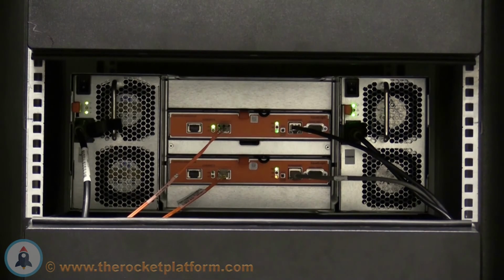In the rear of the machine, you will see the control modules. The faulty control module is in the secondary state now and will have a green light for the PWR and an amber light for the ACT. If the control module is in the not installed state, the controller will have a green light for the PWR and a red light for the ERR.